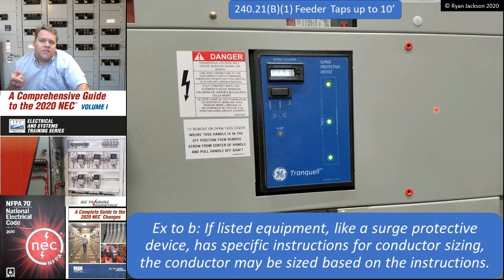There is an exception to how I size 10-foot taps. It says if listed equipment like a surge protection device has specific instructions for conductor sizing, then the conductor can be sized based on the instructions. I'm not a huge fan of this language, listed equipment. I mean, listed equipment could be anything, any equipment that's listed, but it says like a surge protective device. And what I think they're trying to say is something that has no real load to it. Like a surge protective device doesn't have a load. So do I really need overload protection for a surge protection device conductor since there's not really a load on it? So if it's a no load piece of equipment and it has specific instructions for conductor sizing, then go ahead and just follow the instructions and don't worry about it.